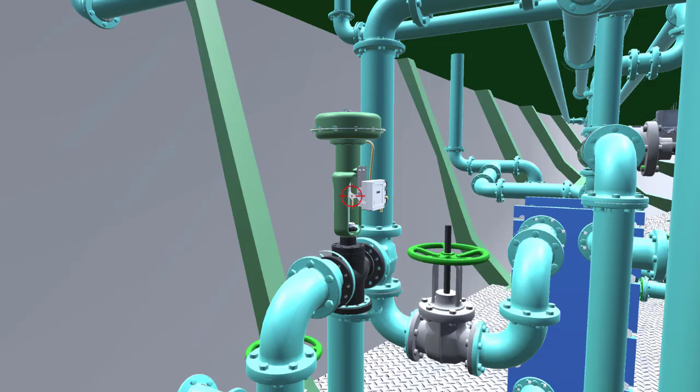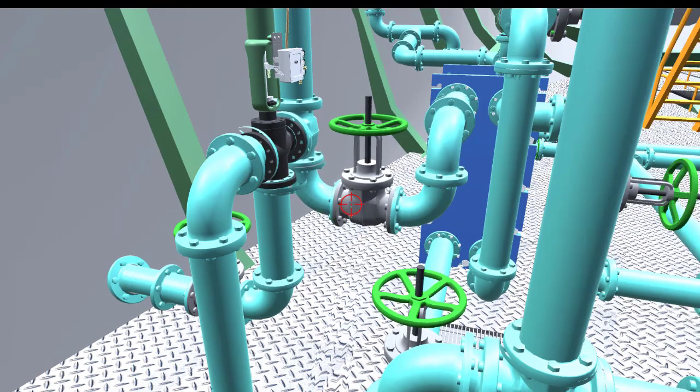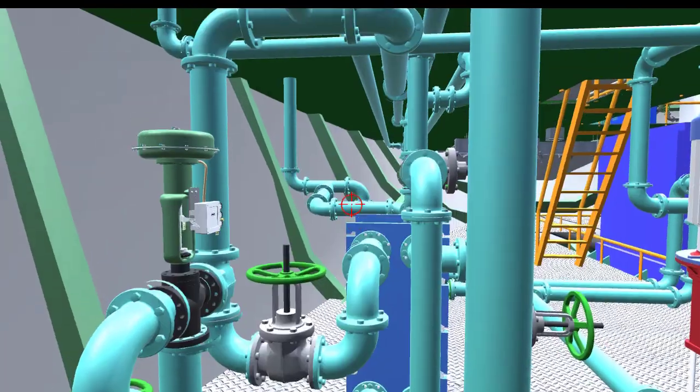It has a three-way thermostatic valve, or we can term it as three-way thermostatic mixing valve. As the word implies, mixing, it's basically mixing the water circulating through the heat jacket exchangers and at the same time mixing it with the water coming from the sea. Seawater is basically used for low-temperature machineries.